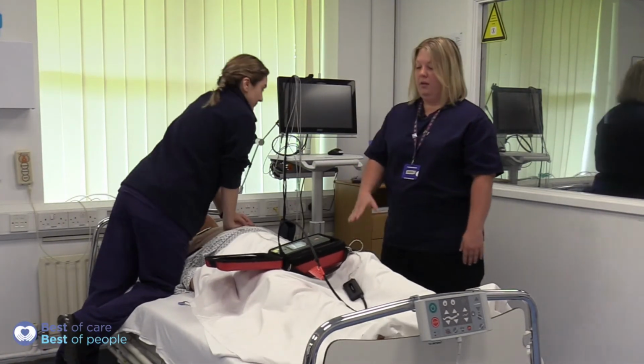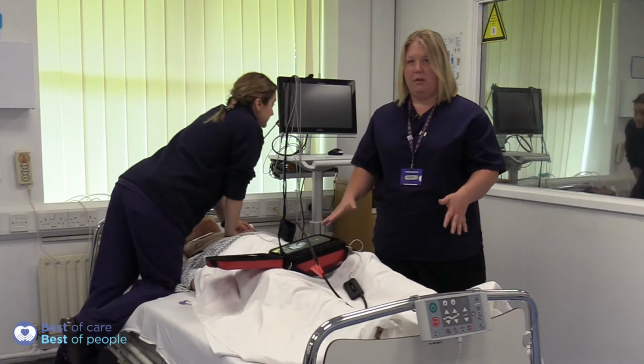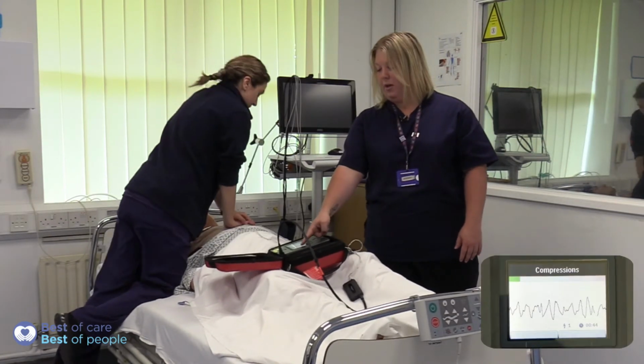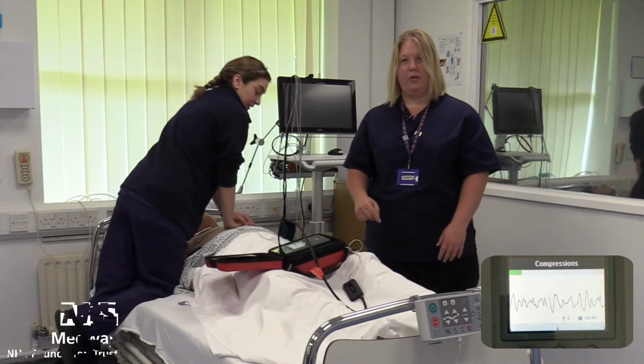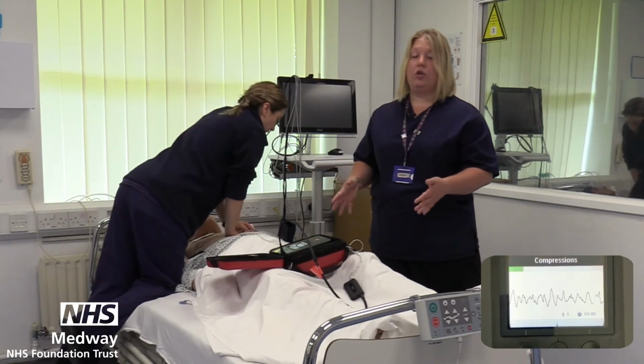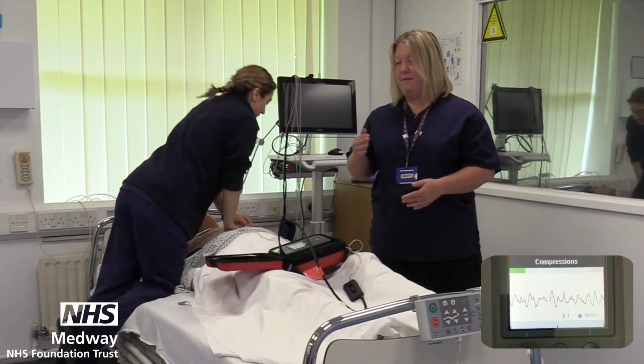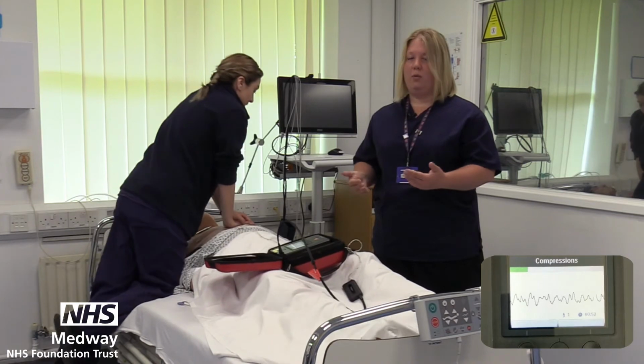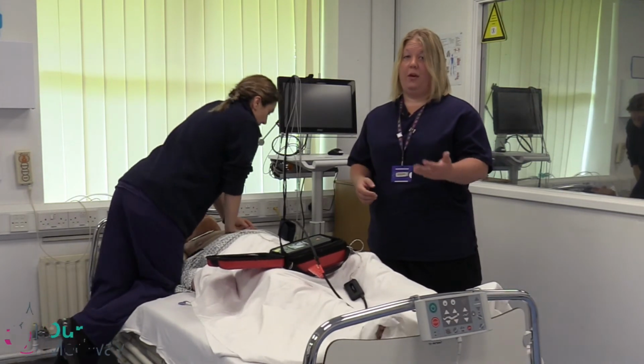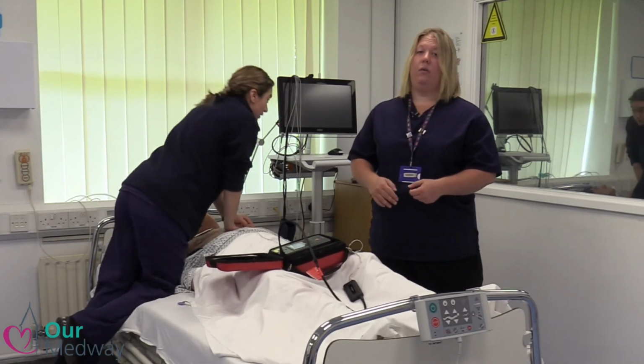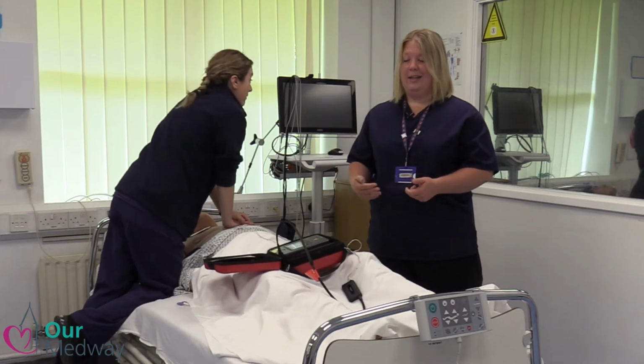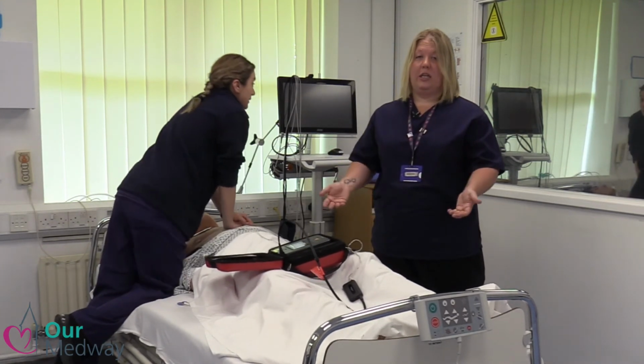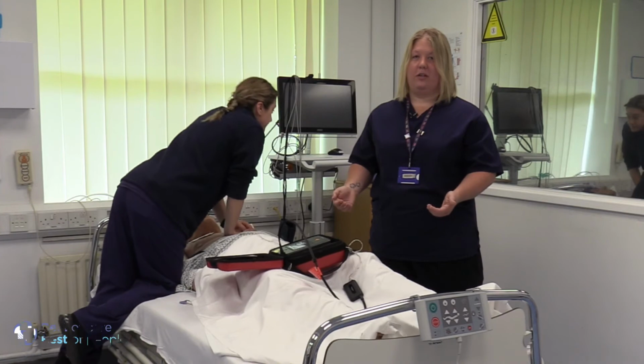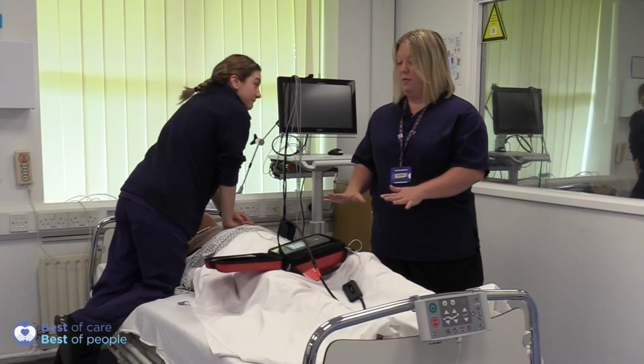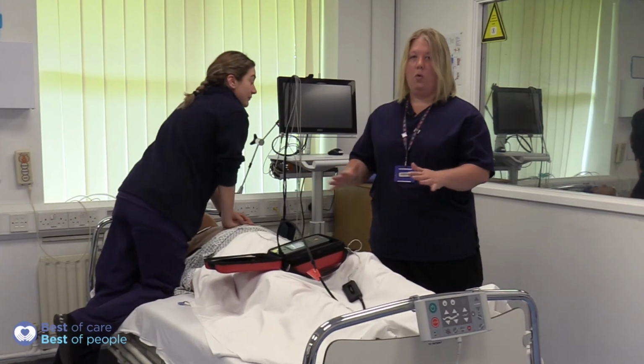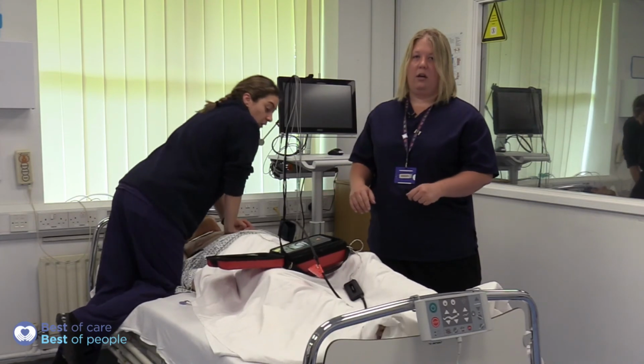This machine will then keep timing for us. You will see a green bar that will start to move across the top of the screen of the defibrillator. This is your 2-minute timing. So every 2 minutes the machine will stop and it will analyse the rhythm. It will advise a shock, as you've just seen, or it will advise no shock. In the instance of no shock, you continue CPR unless there's an obvious sign of life. So we keep the defibrillator on and the pads on all the time that we are running the cardiac arrest.